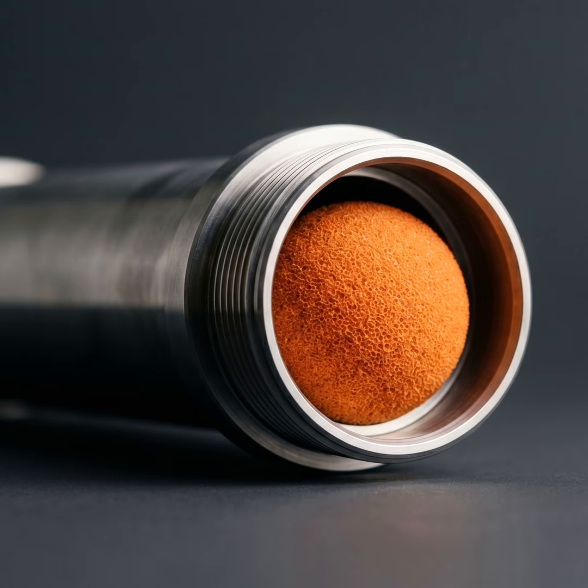Precisely. The wet bulb temperature is a highly specific measurement that accounts for both the actual air temperature, the dry bulb, and the humidity. Okay. It represents the absolute lowest possible temperature to which water can be cooled through evaporation in those specific immediate atmospheric conditions. The lowest possible temperature? Yes. You cannot cool water below the ambient wet bulb temperature, no matter how hard you blow air on it, no matter how much you try. It is a hard limit imposed by the unbreakable laws of physics.